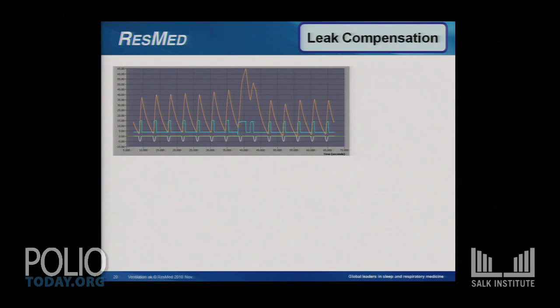In this example, we're looking at another example of a leak being created. Here we have the patient effort along this bottom line. The next line, the blue line, is the inspiratory pressure, the IPAP pressure, and then the volume that's delivered to the patient. So we created a big leak, again, right here. And when we created that leak, do you notice the ventilator gave one extra breath before the patient asked for it, because it saw that big leak and thought that was the patient asking for a breath. So that's an opportunity for dyssynchrony. We have a big, giant leak, so we have an extra long breath, and then what we call one auto-triggered breath, and then we're back in sync pretty well.